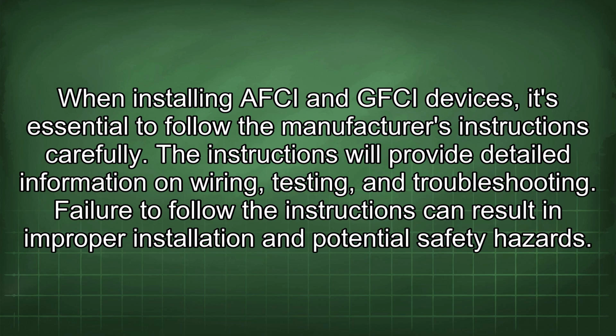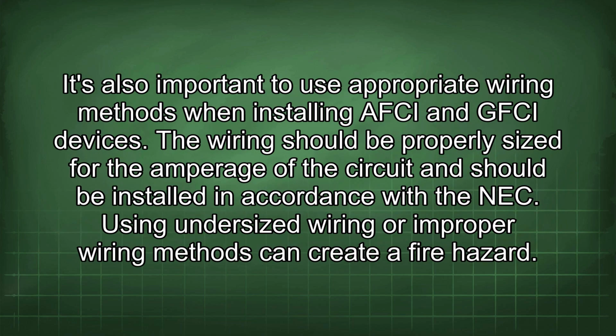When installing AFCI and GFCI devices, it's essential to follow the manufacturer's instructions carefully. The instructions will provide detailed information on wiring, testing, and troubleshooting. Failure to follow the instructions can result in improper installation and potential safety hazards. It's also important to use appropriate wiring methods. The wiring should be properly sized for the amperage of the circuit and should be installed in accordance with the NEC. Using undersized wiring or improper wiring methods can create a fire hazard.